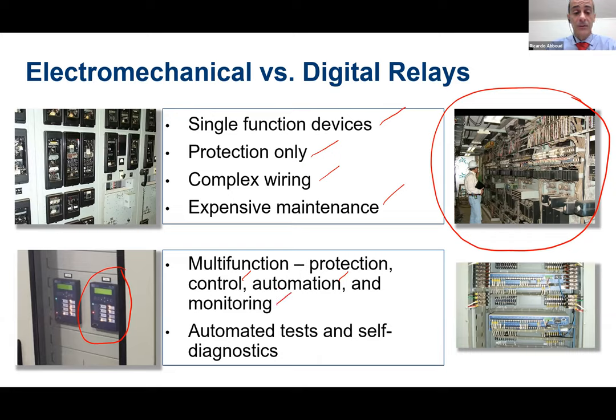Okay? And also monitoring. So we can use a digital relay to monitor circuit breakers. We can use digital relays to monitor the DC system or the battery system in the substation. And the relays have self-diagnostics or self-test. So this can reduce the maintenance that is necessary because the relay is no longer so quiet. The relay will speak up when there is an internal problem in the relay. So it's totally different from the electromechanical, where in the case of a failure in the electromechanical relay, you are going to find that failure during the maintenance or when it's necessary to trip and the relay does not trip, or you have an incorrect operation of the electromechanical relay.